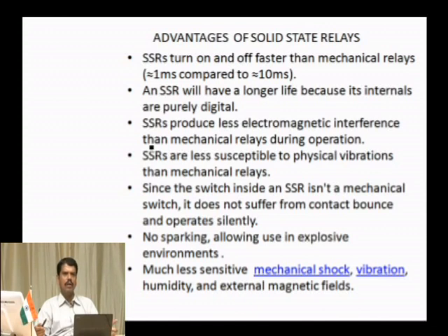There are no electromagnets involved and no mechanical parts, which is why there is no electromagnetic interference. They are less susceptible to physical vibrations and are very insensitive to them. The switch inside is not a mechanical switch, so there is no bouncing and no noise, and they operate silently. There is no sparking, so they can be used in explosive environments. They are very insensitive to shocks, vibrations and humidity, and external magnetic fields do not affect them. These are the various advantages.